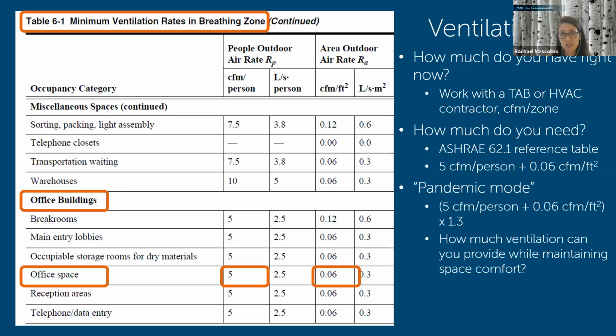This is a screenshot from the ventilation rate table from ASHRAE. It's organized by occupancy type. And you can easily put a metric on what is the minimum amount of ventilation, the volume of air that I need to be introduced to a space based on the type of the space. So here I just picked office space. We know that you need 5 CFM for every person that's in that space, plus an additional 0.06 CFM for every square foot of area.